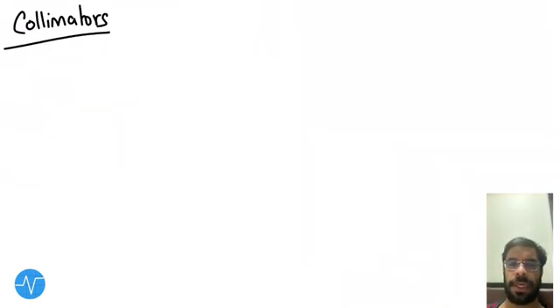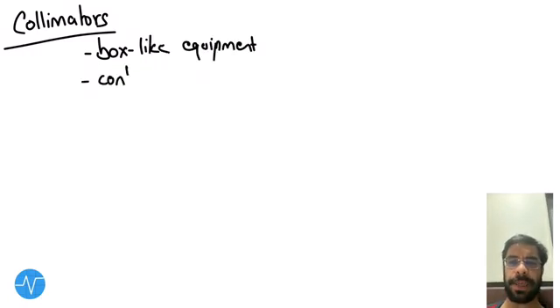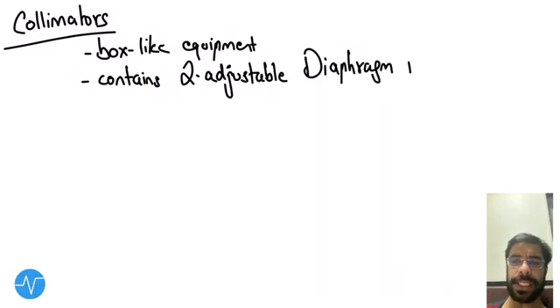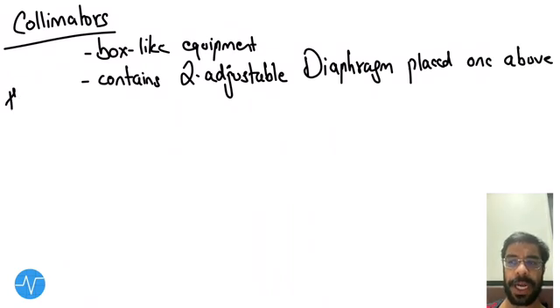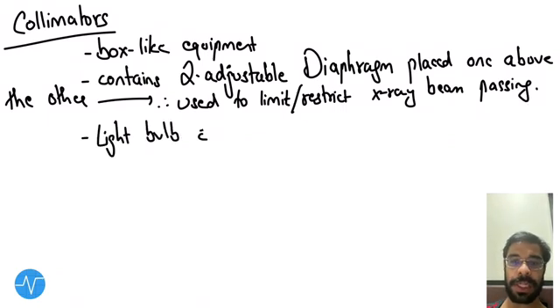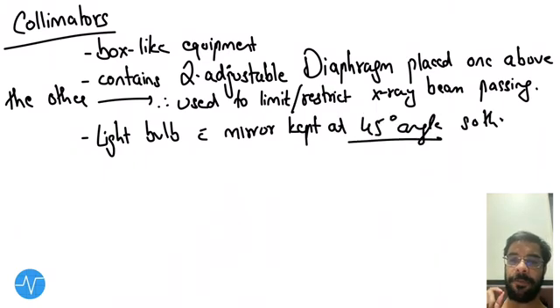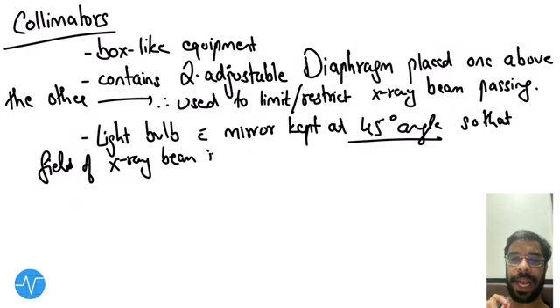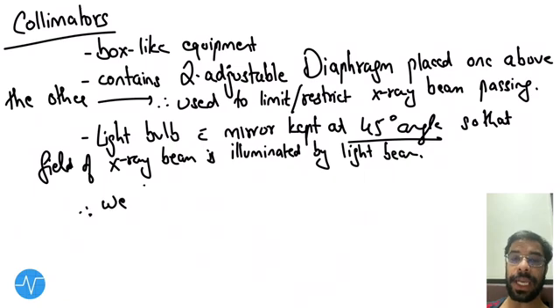The third beam restricting device is the collimator. It is a box-like equipment that contains two adjustable diaphragms placed one above the other, which limit or restrict the x-ray beam. There is also a light bulb with a mirror kept at a 45-degree angle so that the field of the x-ray beam coming out is illuminated.